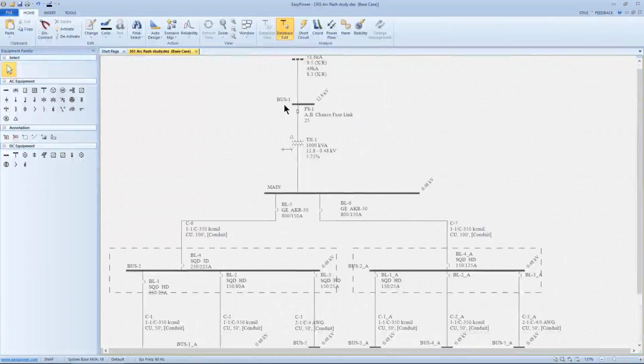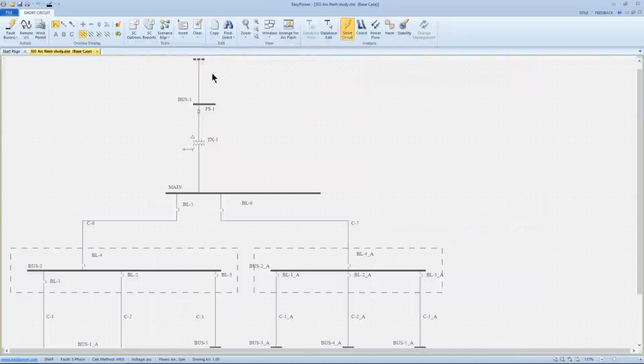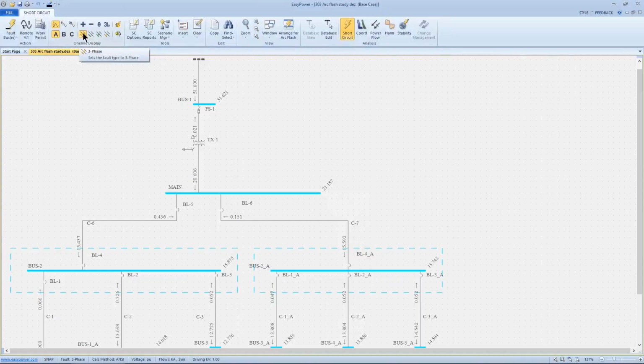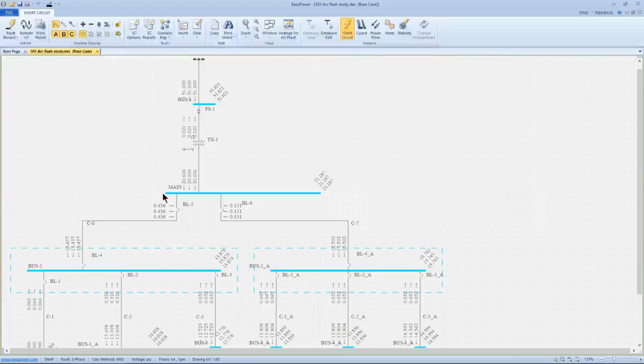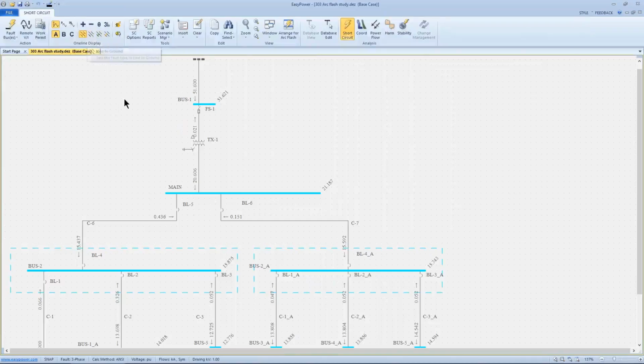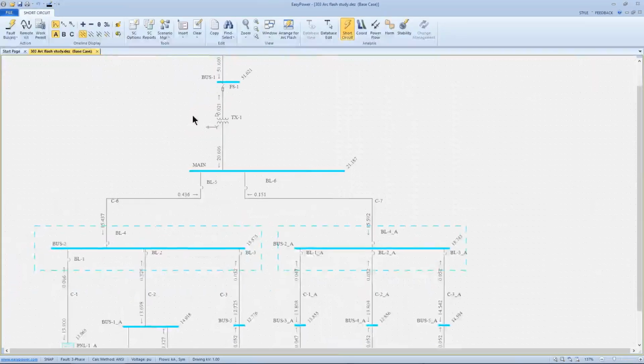So here's a typical one-line diagram, and when we go into short circuit focus, we're looking at the second line of the ribbon up here, the types of faults that we're generating. So if we fault all the buses, we're looking at the A phase and a three-phase balanced fault. And it behooves us to look at just a single phase because by definition everything is equal and there's no need for the redundancy. So this again is the only balanced fault that is used for arc flash calculations.